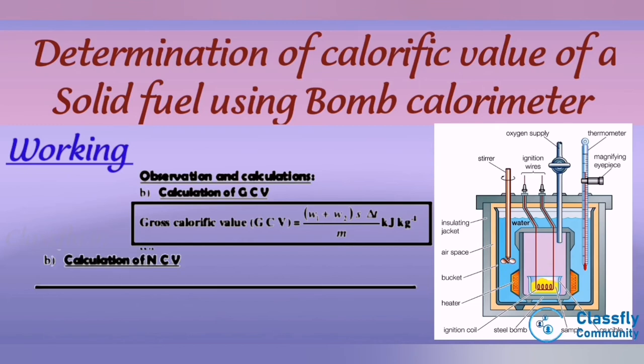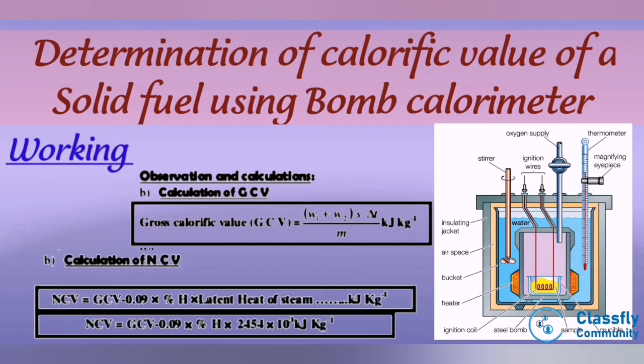The calculation formula for net calorific value is: NCV = GCV − 0.09 × (percentage of hydrogen) × latent heat of steam. That is, NCV = GCV − 0.09 × (percentage of hydrogen) × 2454 × 10³ kilojoules per kilogram.